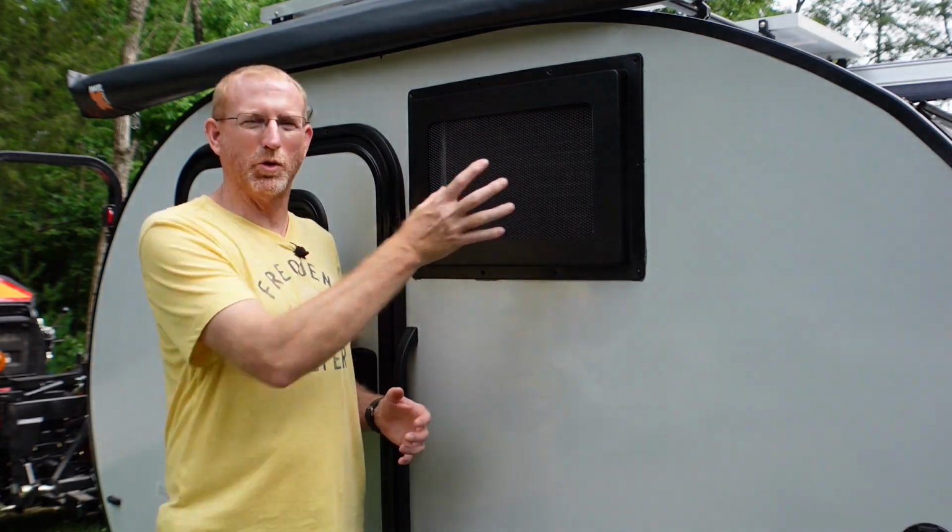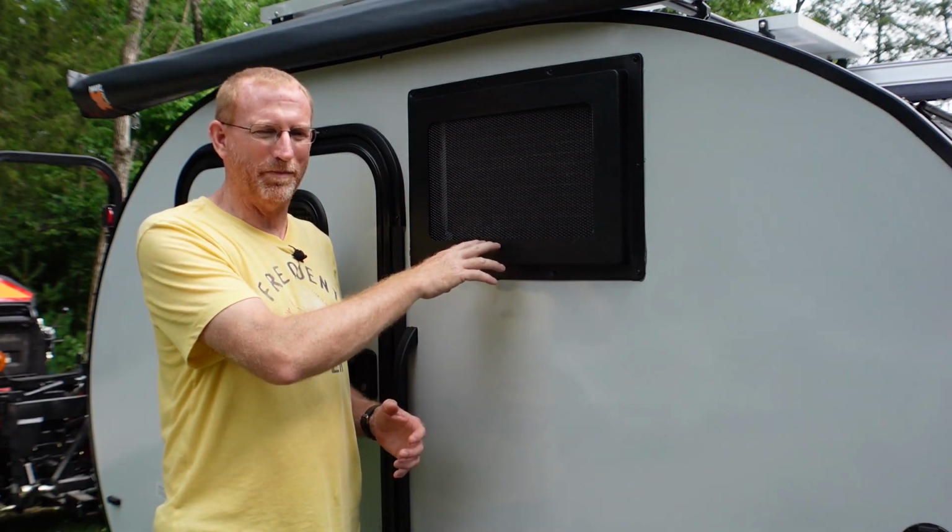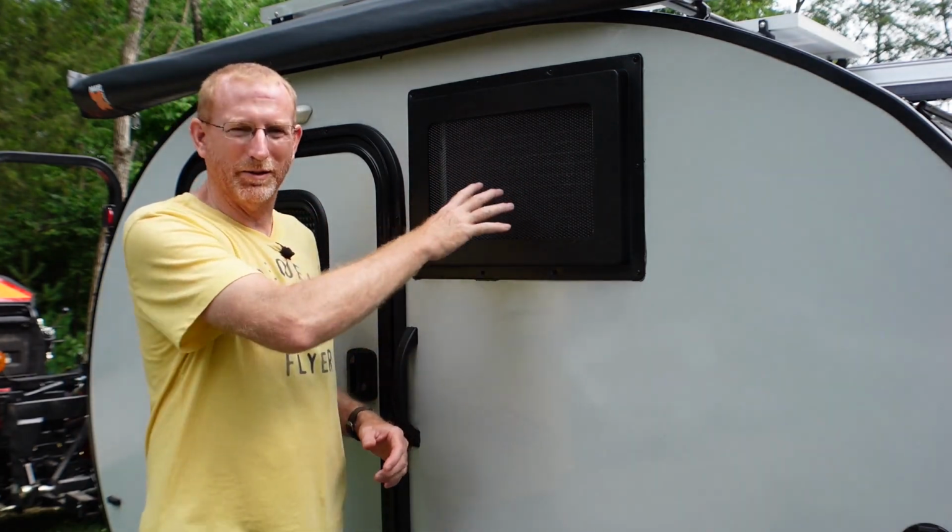That slinger fan isn't exactly 100% accurate. You know, it throws the majority of it through this condensing coil, but it also slings the water to the outside and over the compressor. That's what it's designed to do. But when it's inside the cabin like this, you don't want that to happen because it's going to sling it all over the inside of the cabinet and then it runs down. Gravity takes over and the water drips out.